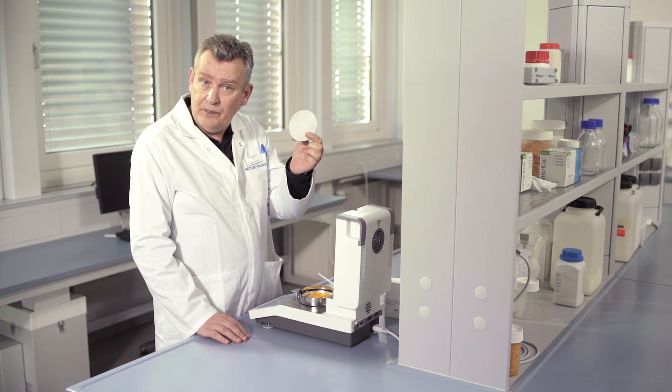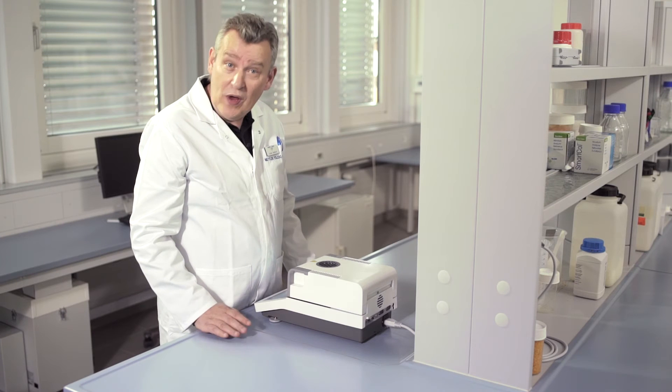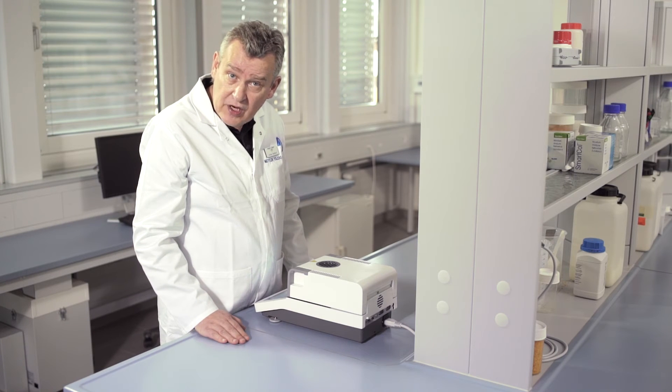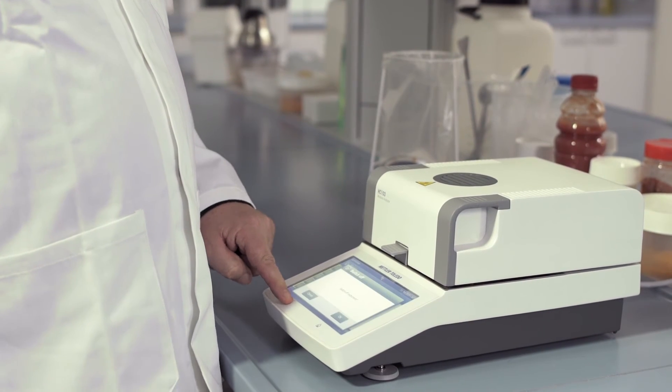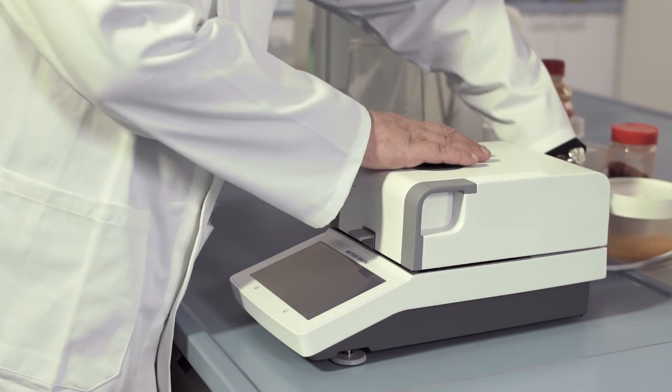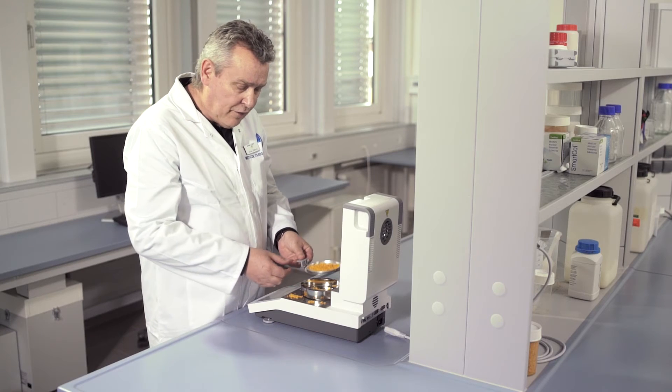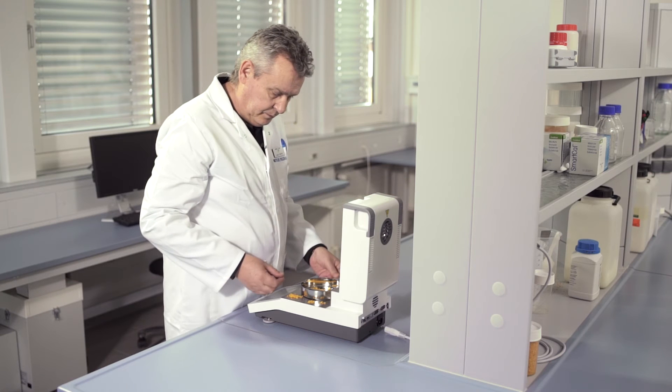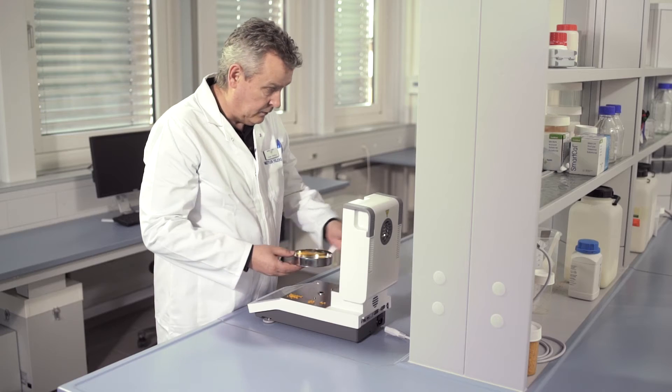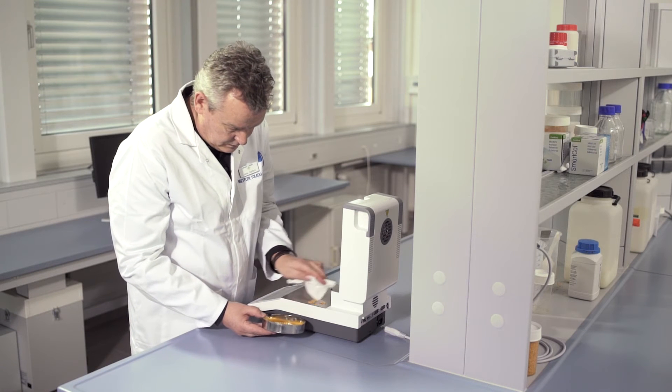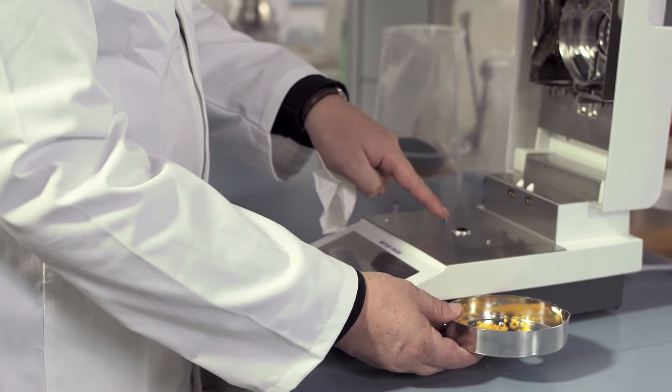Finally, after a long working day and intensive use of your instrument, the last job is to clean up and get the instrument ready for tomorrow. First, switch off the instrument and remove the power supply. Then remove your last sample, remove the pan holder, and clean the surface, making sure that nothing goes into the hole in the middle.